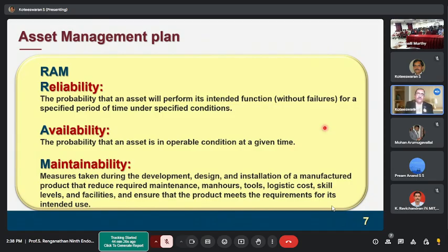This we always need to keep in mind - we call it RAM design. It's applicable for any kind of equipment or manufacturing, even applicable to our own personal life. RAM: Reliability, Availability, Maintainability. That means whatever instrumentation is used or deployed to control the plant, the first question is: is it reliable? What does reliability mean? It's the probability that an asset will perform the intended function for a specified period of time under specified conditions. Or in simple words, whenever we buy a product, we check the warranty and guarantee - that's what it is. It means without any failure for a specified period, the instrument asset is supposed to work.